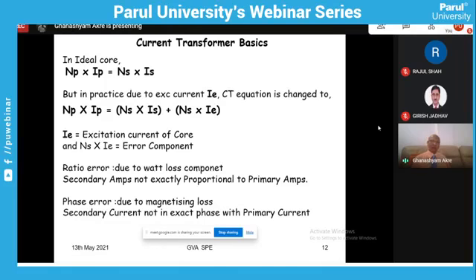Now the scenario is changed. You can see it is not balanced exactly as an ideal transformer. Here the error has been introduced by NS into IE because it is the extra current it is drawing. For example, if it is 100 by 1 ampere, then because of the excitation current, the primary will possibly be 101 ampere and the secondary will be 1 ampere. Because that 1 ampere in the primary is drawn by the core to maintain the flux and errors and losses of the core. So that means your ratio now becomes 101 to 1 ampere, not 100 by 1. So that is how the error is very important.